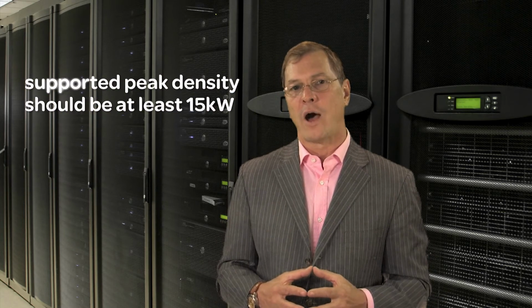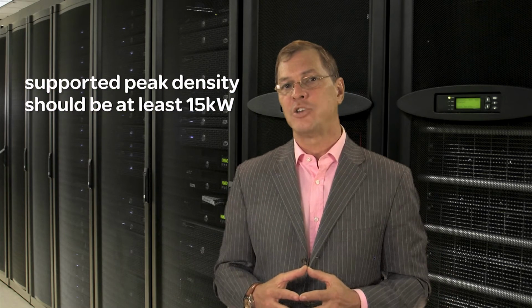And as far as the peak rating of the density, it ought to be at least at the 15 kilowatt level. But you could easily imagine us designing today a data center designed more for 12 or 14 kilowatts average and 30 kilowatt peaks. But that wouldn't be common and probably not recommended at this stage for a data center being built today. So upping the density from what your historic trends were, particularly the peak power density capability within the data center, is going to be important for new data centers.